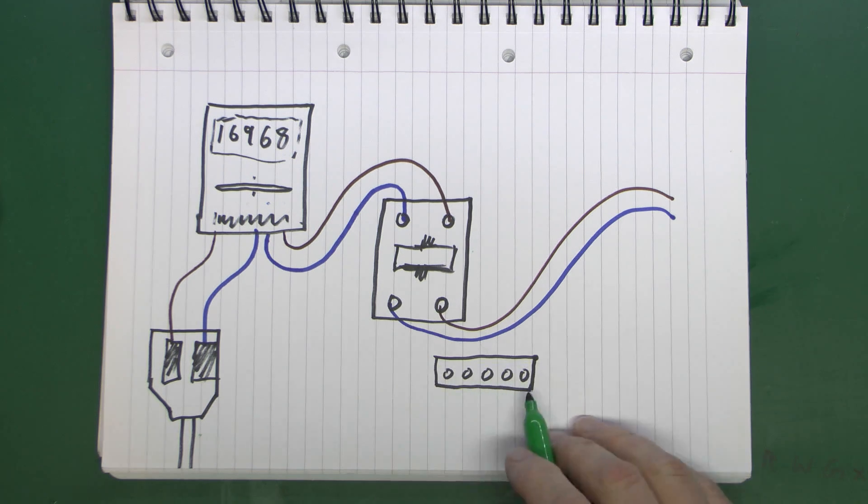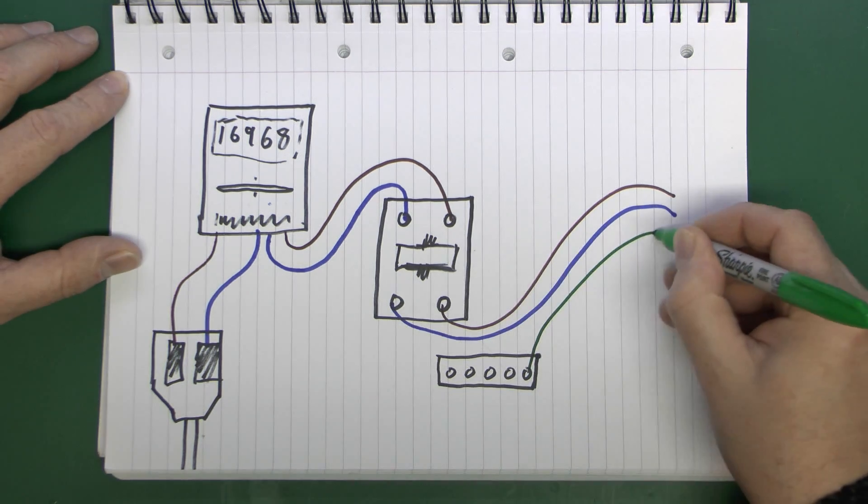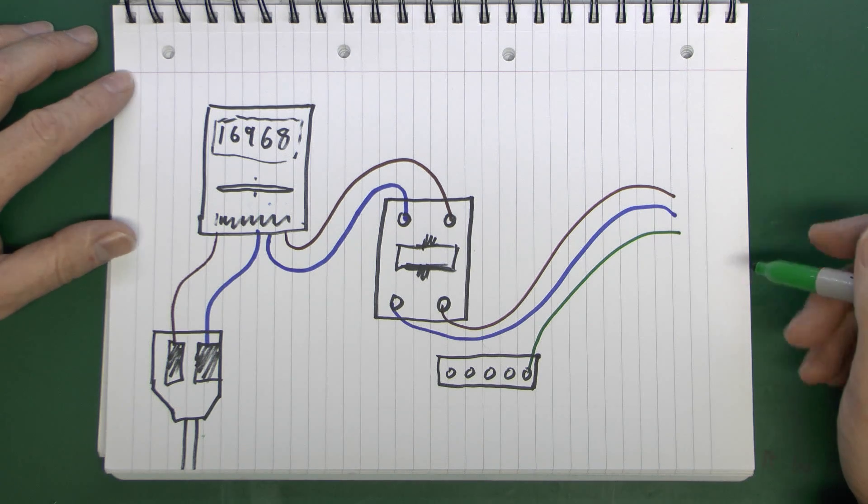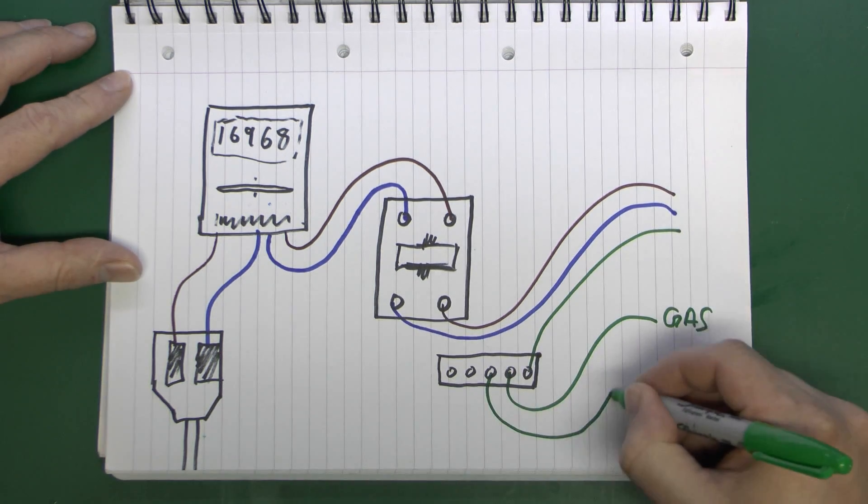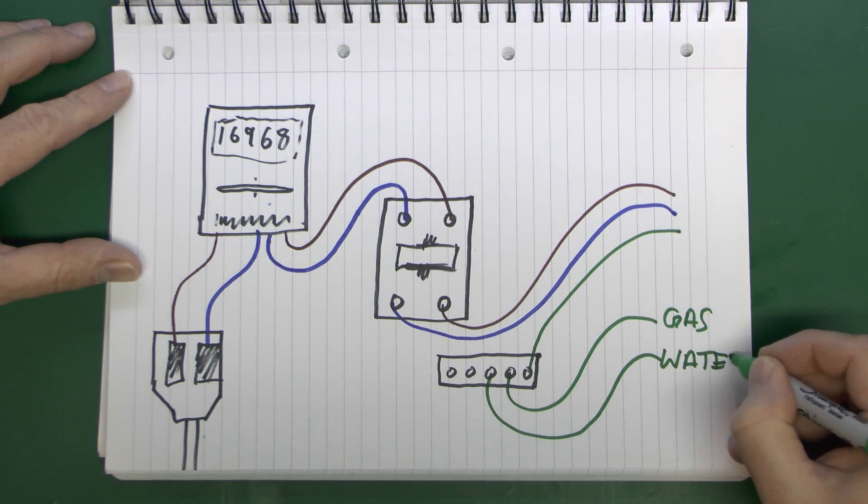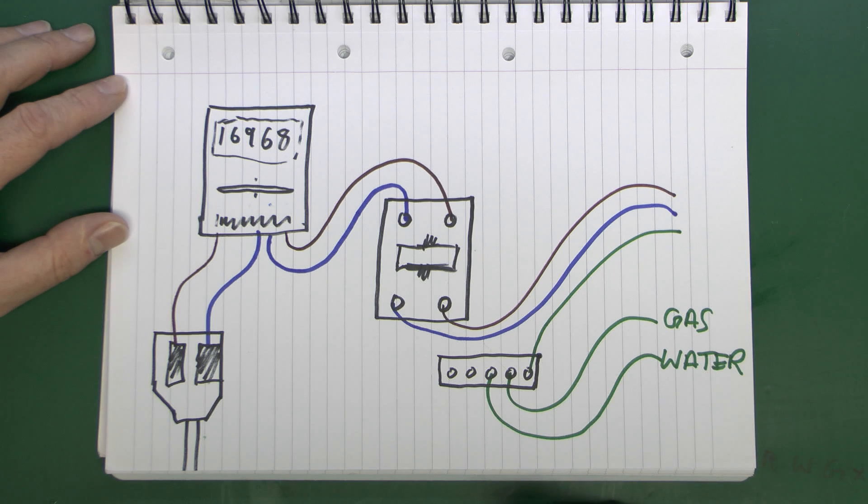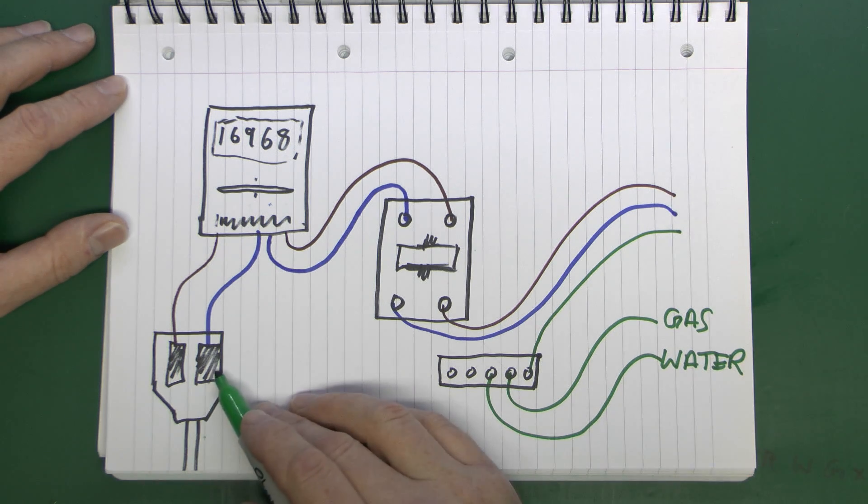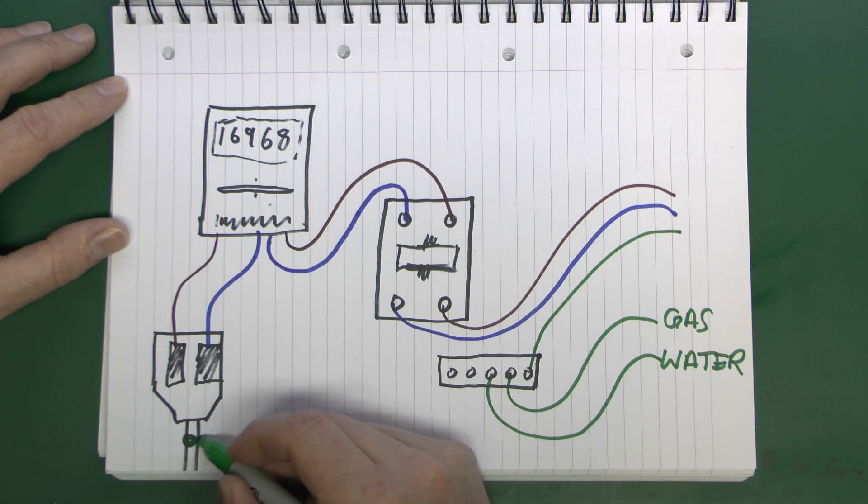Then in this case we've got the wires just going over to your consumer unit or whatever, and the earth in this case is a separate bar here, again that could be part of the consumer unit or contained inside of it. Connected to here you're going to have the wire going across to your consumer unit and the thing for the installation. You're probably also going to have wires for your main bonding which will be things such as gas pipes and water pipes and possibly other things as well if you have oil supplies or whatever and structural metalwork and all that other kind of stuff. So there are quite a few wires connected in here. The earth wire itself will either come from the supplier's cutout here, combined with the neutral, possibly from the actual cable itself if it's an older installation, or in some cases actually from a rod in the ground you have to provide yourself. In this case let's just show it coming from the cable there.